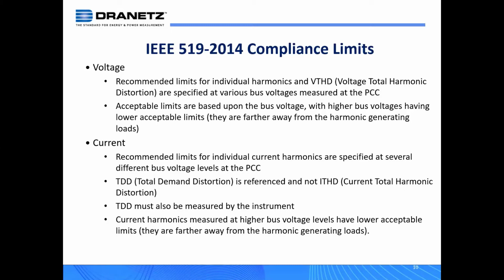However, for current, one of the changes in the 2014 version is that we're not looking at current THD, we're looking at total demand distortion. And TDD takes into account the overall capacity of the system. So we're not looking at individual THD, which doesn't reference the capacity of the system. We're looking at harmonics based upon the overall capacity of the system. So a low amount of harmonics on a high capacity system are not really a big deal. But if you have high distortion and the amperage is high compared to the capacity of the system, well, that becomes more and more important.